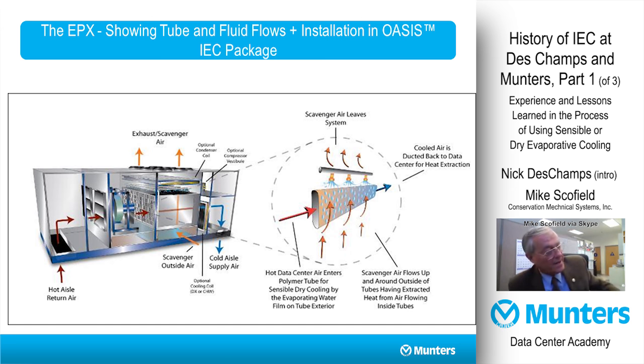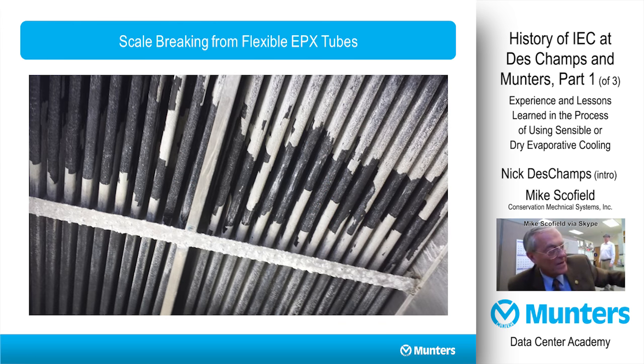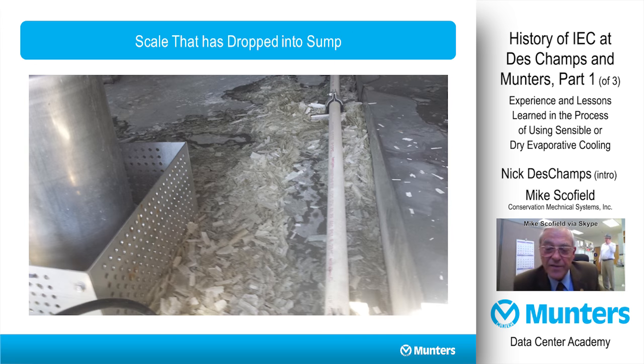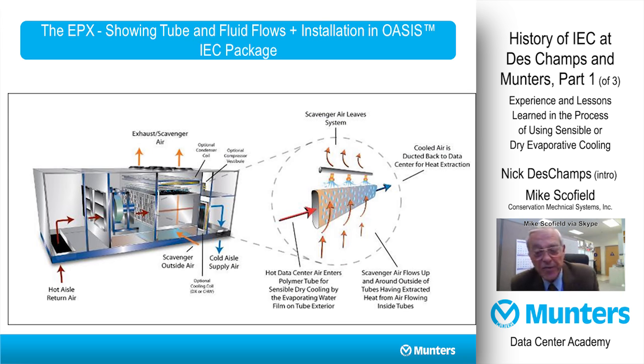So these figures that show the shedding of that onion skin, and I think we refer to it as water hardness buildup on the wet side of the tube, pretty much visually tells the story of what's going on inside that heat exchanger, allowing the system to maintain full effectiveness even after years and years of service. I think this is the tremendous breakthrough.